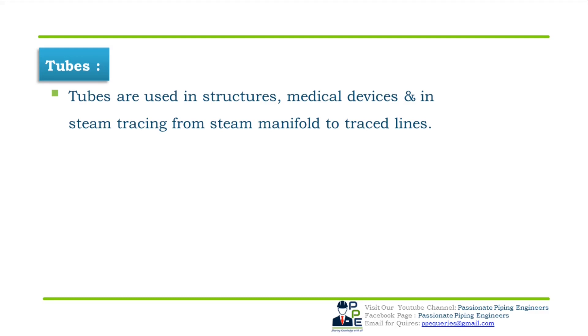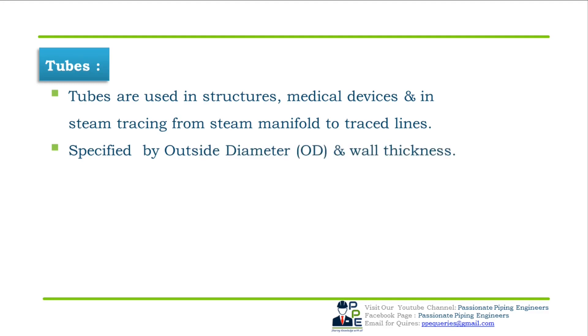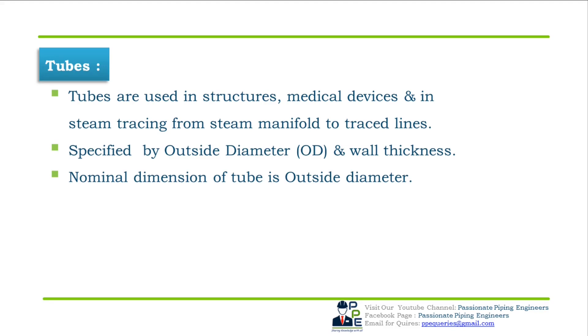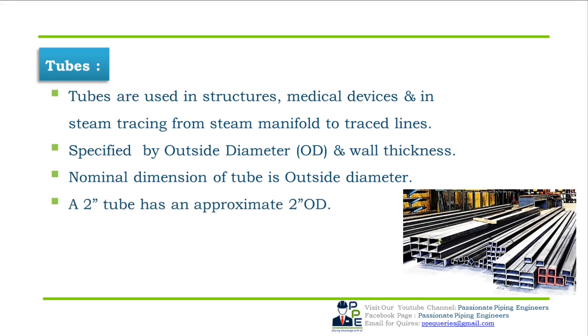Tubes are used in structures, medical devices, and steam tracing. They are used for fittings for steam manifolds to trace lines. Tubes are specified by outside diameter (OD) and wall thickness. The nominal dimension of a tube is its OD — a 2 inch tube has an approximate 2 inch OD.